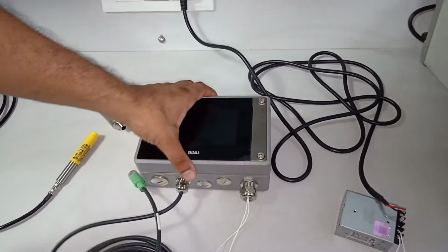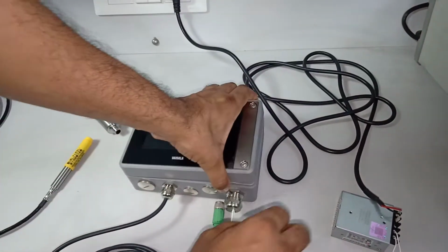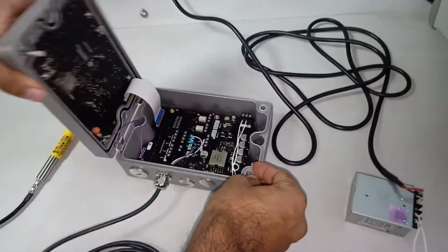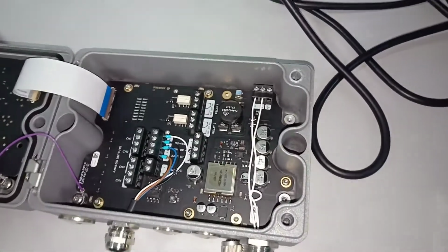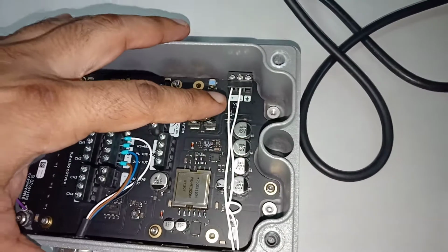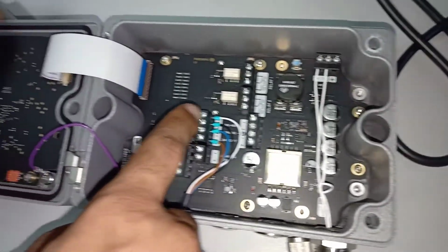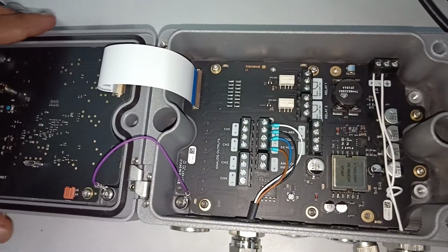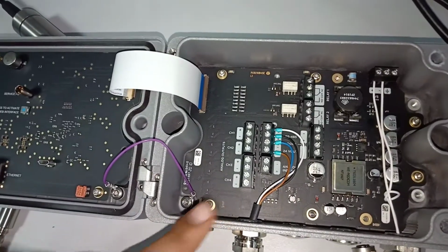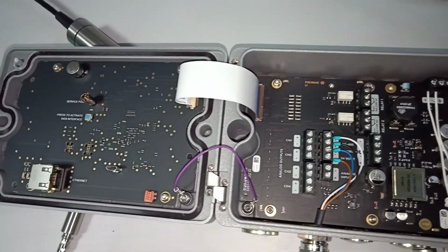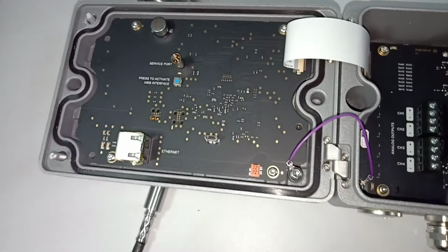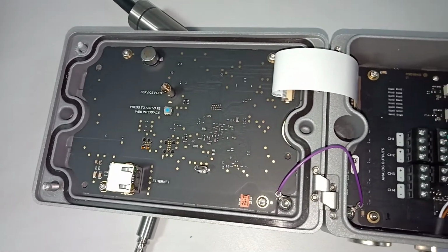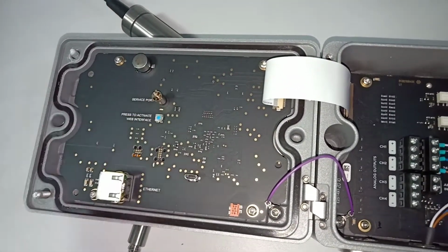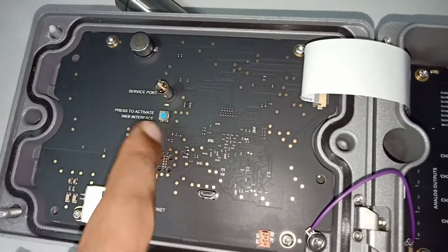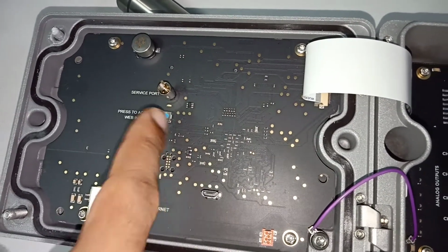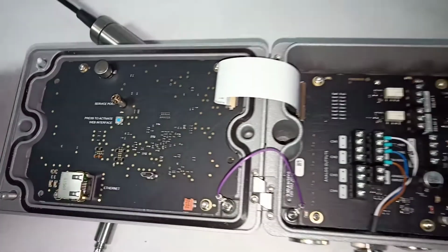This is Vaisala Indigo 520 probe transmitter. So this is the unit. You give in 24 volt DC and you can get RS485. You have an option to connect another probe, so you can connect two probes at a time for RHT, CO2, hydrogen peroxide. Now we have this service port to calibrate, and you can just plug in the Ethernet and get the readings on your local server as well.